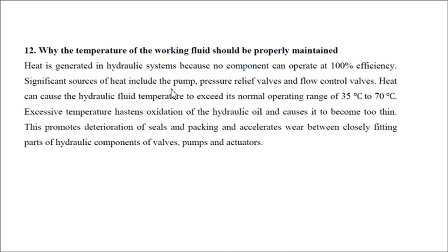Significant sources of heat include the pump, pressure relief valve, and flow control valves. Heat can cause the hydraulic fluid temperature to exceed the operating range of 35 degrees Celsius to 70 degrees Celsius. Excessive temperature hastens the oxidation of the hydraulic oil and causes it to become too thin.